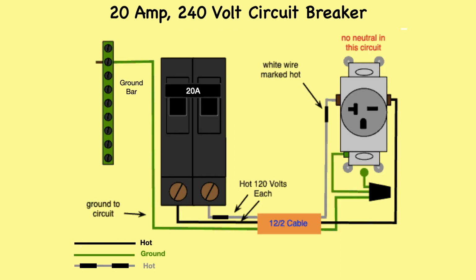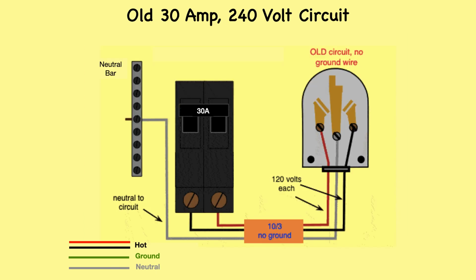This circuit breaker wiring diagram illustrates installing a 20 amp circuit breaker for a 240 volt circuit. The 12-2 gauge cable for this circuit includes 2 conductors and 1 ground. The white wire is used as a hot in this circuit, and it is marked with black tape on both ends to identify it as such. A neutral wire is not used in this circuit. A dedicated 20 amp circuit like this is used for heavy household appliances, like large portable window air conditioners. This is an outdated circuit that may still be used in some situations.